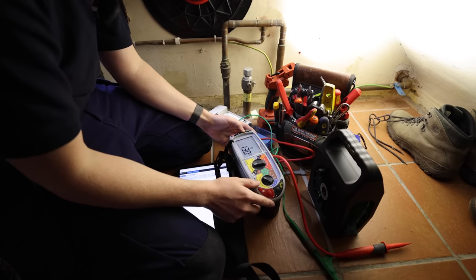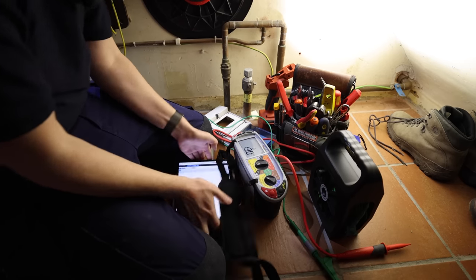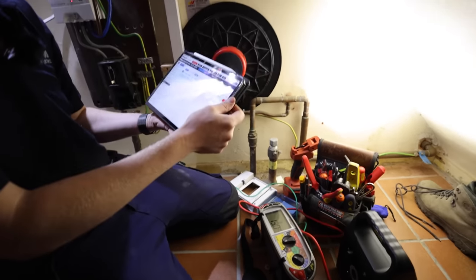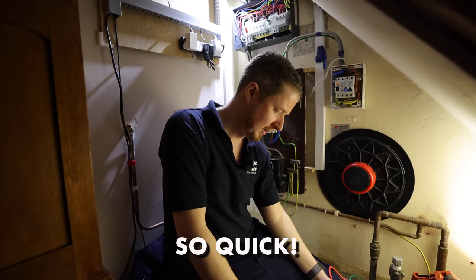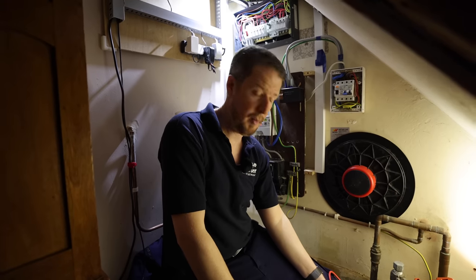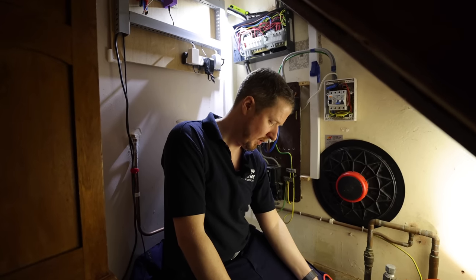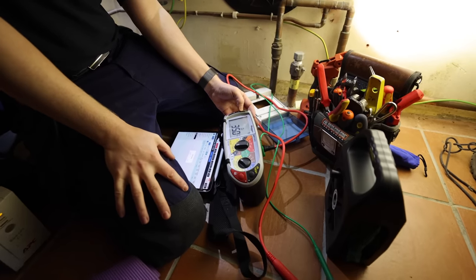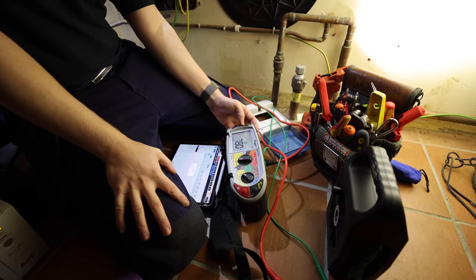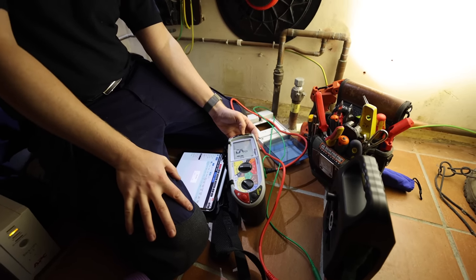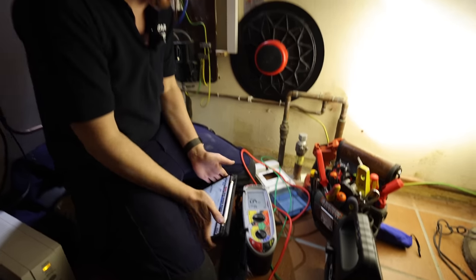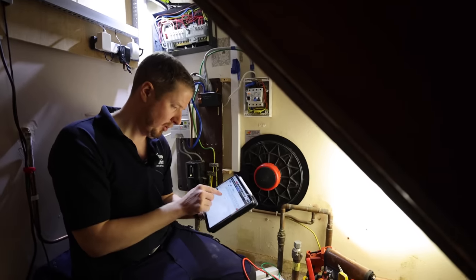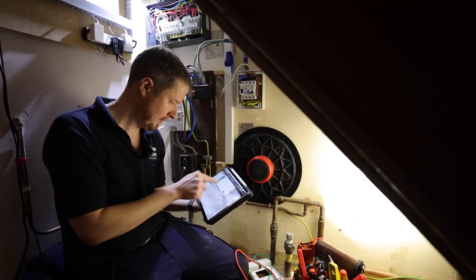So we've got 23 milliseconds, 32, so that's the one that we'll record. And then at five times we've got 4.7 and 13, so we've got 32 and 13 to record. Yeah, the RCD testing on this Megger is so quick, it's the quickest I've ever experienced from any MFT. So we've got 25.8, 35, so we record 35, that's the highest. And then we got 7.8 and 15.1, so 35 for one times and 15.1 for five times.